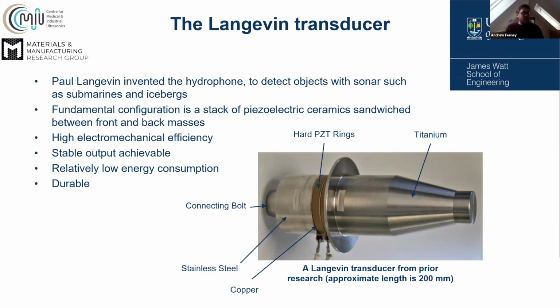The fundamental configuration is a stack of ceramics, like we see here. So this is a transducer I built a few years ago for the subsea ultrasonic technology project, and it's sandwiched between front and back masses. So this whole transducer is tuned to operate at a specific frequency and a specific mode of vibration. This transducer here was designed using finite element analysis, and at about 20 kilohertz it will operate in a longitudinal motion, so it will vibrate in a longitudinal mode.